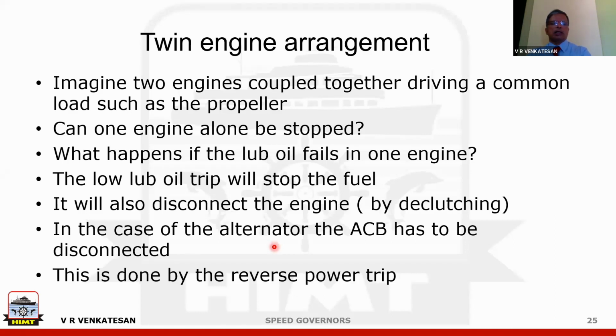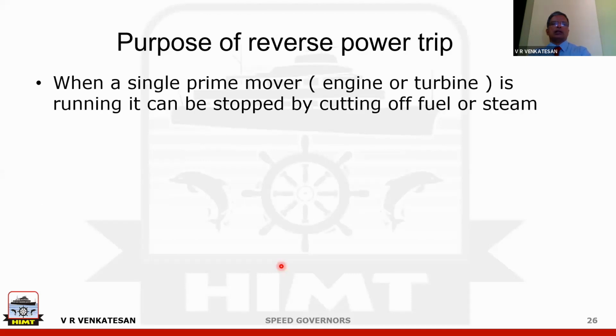This is the way you have to understand reverse power protection. It is done by the reverse power relay, which detects this. So power becoming reverse is a very simple thing to understand. Why does the power become reverse? It will become reverse only when the fuel is reduced below the idling levels. In a normal circumstance, this would happen because of a fault or because the fuel filter is clogged, any such reason. We are simulating the same thing by deliberately reducing the fuel. So it is the same thing.